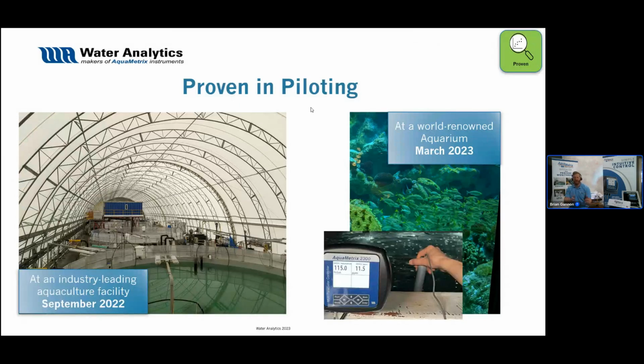Over here on the left, you can see one of the world-class aquaculture facilities. We were able to install one of the ODO-TXs in there, and that one's been working successfully for almost a year now. A really great story with this one, as I mentioned at the ODO webinar, is we installed this sensor here, and unfortunately we lost track of where it was compared to all the other ones. The only way we found it several months later was it was the only sensor that didn't need to have maintenance performed on it. It didn't need to be checked to see that the calibration had drifted. It continued to operate exactly as it wanted to.